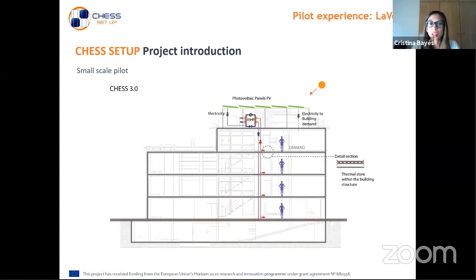So the final solution is that one, and keeps the photovoltaic panels as the energy production side of the system that feed an air source heat pump that heats the thermal storage, which in this case is the thermal mass of the building slab. So it's where the heating floor is already installed. With this solution, no thermal energy is wasted. It supplies the entire building, and energy savings are greater than estimated previously.